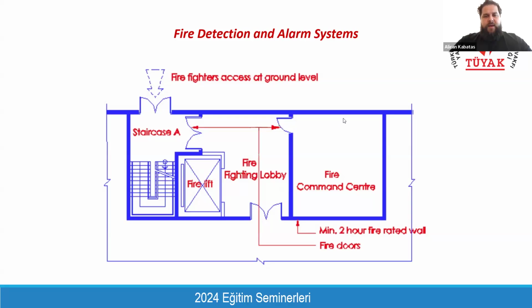the fire pump room. It should be accessible at any point, at any time, even if the building is having a fire incident. We should reach the fire command center easily and by a safe way. And this room should be 2-hour fire rated so that it will not be affected by a fire incident. And it should have direct access from a staircase so that the fire brigade or technical staff of the building can reach it easily and safely, even in case of fire.